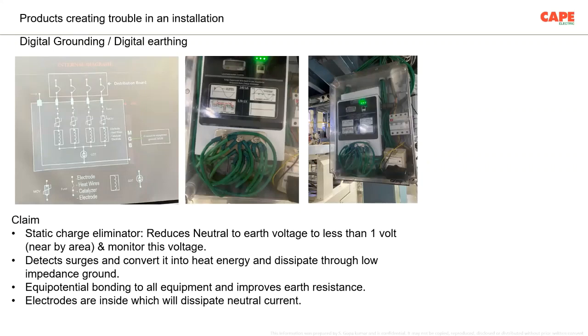One of the products which already created trouble in the market and is going to create more trouble in future is the digital grounding system, or digital grounding. If you Google, you will be able to find more information. The companies claim that this equipment is directly from God. It saves all your electrical safety problems. It saves all your equipment problems. It is a static charge eliminator. It reduces neutral to earth voltage. It detects surges and converts them into heat energy. Equipotential bonding is done. Earth electrodes are not required. And whatever electrical trouble you think of in your mind, there is a solution with this particular device, is the claim of the manufacturer.